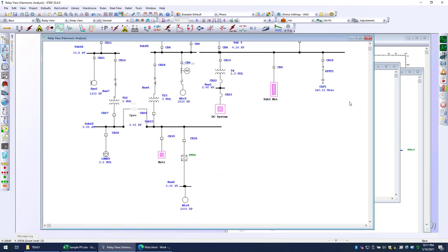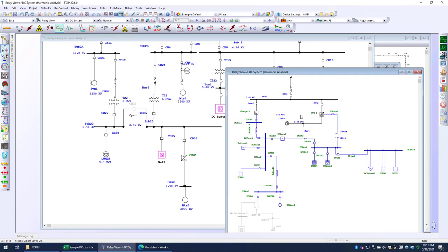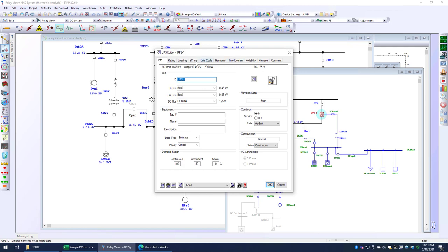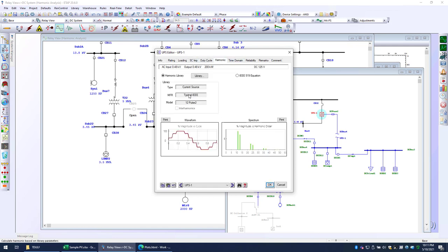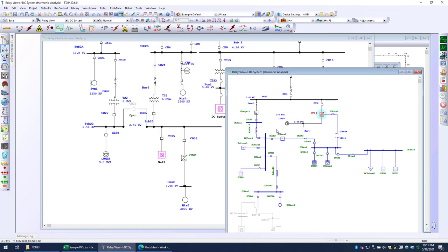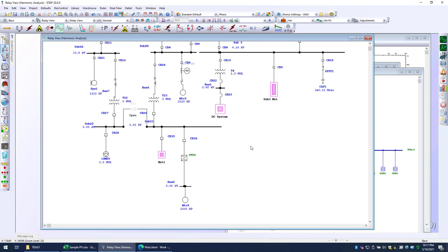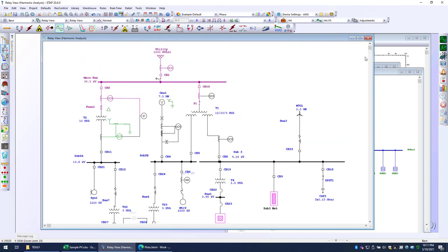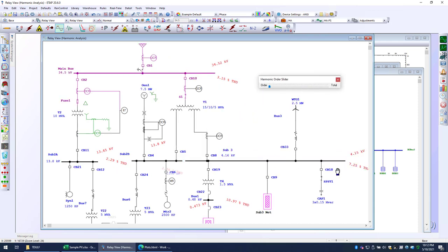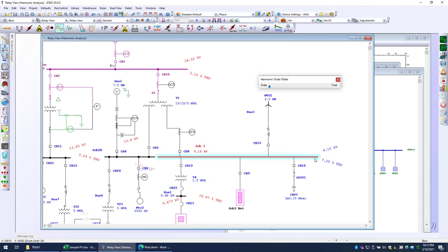If I go into this particular location that has, for example, a charger and a UPS, you can also see that these are harmonic sources. This is a typical IEEE 12 pulse. So all of these harmonic sources will have an impact on my total harmonic distortion. For that, we're going to go ahead and run a harmonics load flow like this. And you notice that at each location, we have a total harmonic distortion. At the point of common coupling, my total harmonic distortion is 3.15. And if I go down into my 4160 volt location, there's a total harmonic distortion here of about 7%.